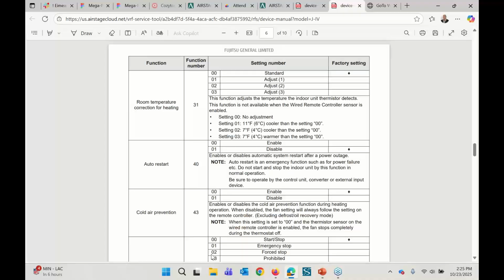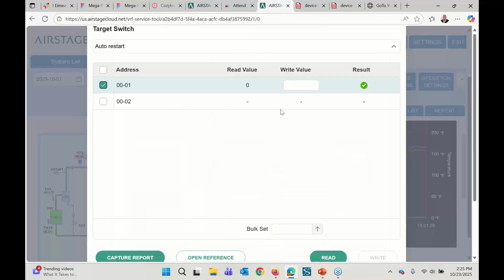Now, I don't tend to memorize all of the function codes, so if I want to find out what that is, I can hit the open reference button down at the bottom. The open reference data takes me to the service manual, and it tells me that with my F40 code, a 0 means that auto restart is enabled.